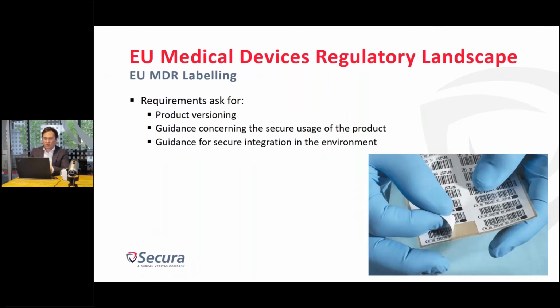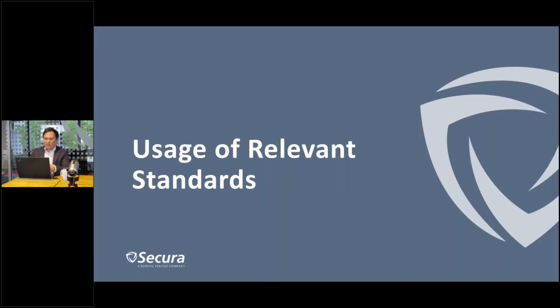Finally, labeling. This is also a topic included in the regulation, and the requirements here are relatively more straightforward than those in the US FDA regulation. Those requirements ask for clear product versioning for both hardware and the software running on top of the medical device, but also clear guidance concerning the usage of the product and the integration of the product in its end environment. If all of that documentation is available and clearly provided by the developer, then the labeling requirements will be met.